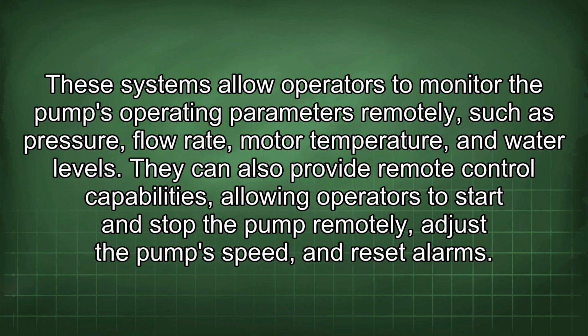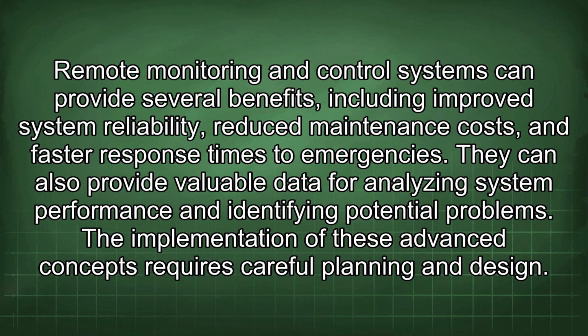These systems allow operators to monitor the pump's operating parameters remotely, such as pressure, flow rate, motor temperature, and water levels. They can also provide remote control capabilities, allowing operators to start and stop the pump remotely, adjust the pump speed, and reset alarms. Remote monitoring and control systems can provide several benefits, including improved system reliability, reduced maintenance costs, and faster response times to emergencies. They can also provide valuable data for analyzing system performance and identifying potential problems.